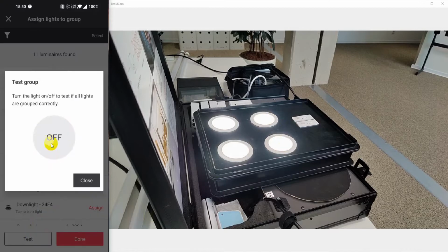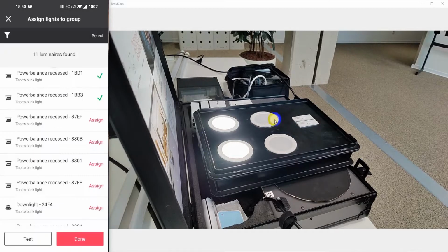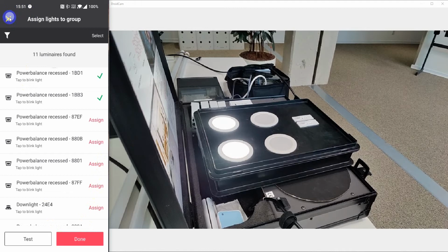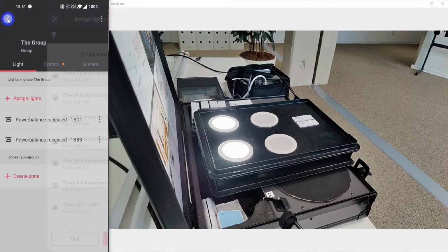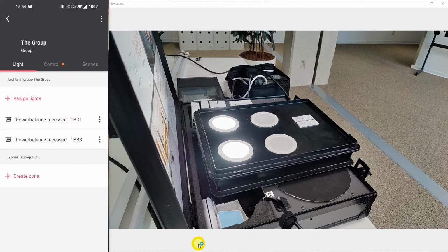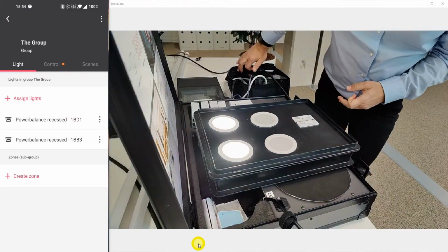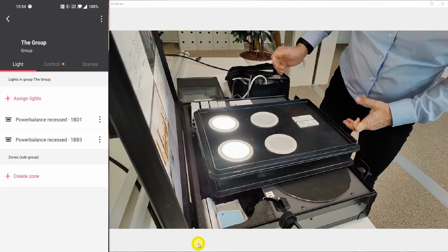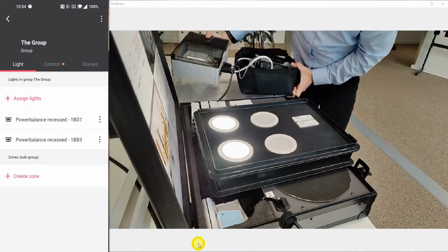Again, this requires you to have access to the power, and then you need to power cycle 5 times within, well, what I was showing was a 3-second power cycle. I believe with the newest firmware you have a 10-second window to power cycle your lights. If I have an RF relay unit, I can also reset that one, but you don't need to use Safemode for this one. It's easier.